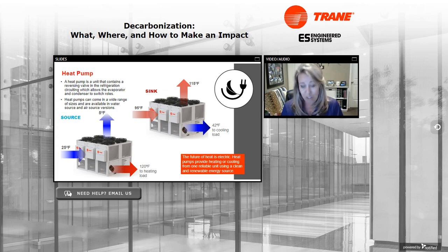So if we move on and talk about heat pumps. Heat pumps can provide hot or cold water. Heat pumps contain a reversing valve within the refrigerant circuit that allows the evaporator and the condenser to switch roles. So when we look at a heat pump's heat exchangers, we like to use the term source and sink versus evaporator and condenser to describe whether it's accepting heat or rejecting heat. Heat pumps come in a wide variety of sizes. We can also do an air source heat pump or a water source heat pump.